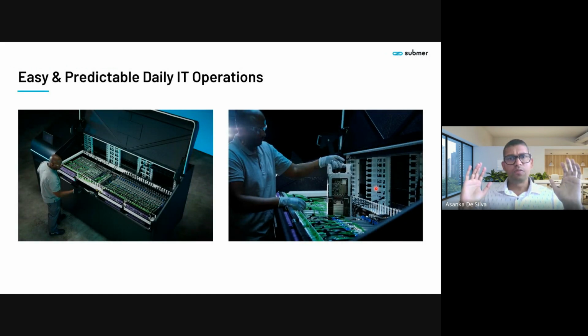Okay, so a little bit more detail on operations and maintenance. Coming back to my point which I mentioned before on myths around maintenance, a few facts. With immersion, as you probably know, the servers do not have fans. And also when you immerse the servers in liquid, you remove dust and you remove moisture from the equation. So what does this mean? You have servers running in dielectric fluid without any moving parts and without dust and moisture. The longevity of the servers increases. Out of our experience, because we have about 400 megawatts of immersion cooling deployed on the ground today, the failure rate of servers is only about 1%.